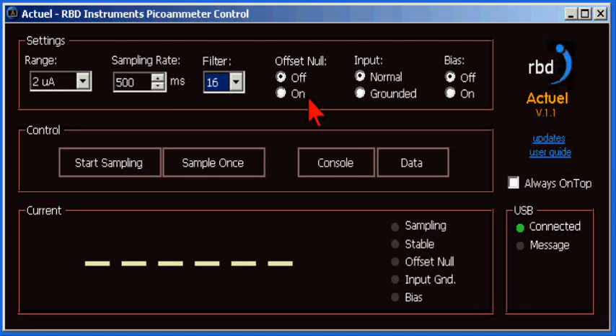The offset null, when selected, subtracts out any leakage current that you may have in your test setup or specimen stage.